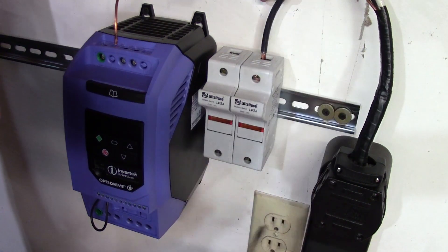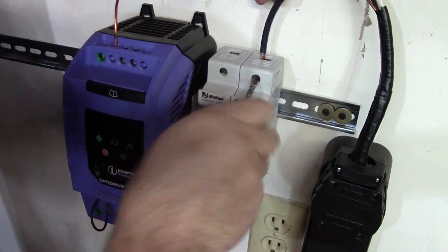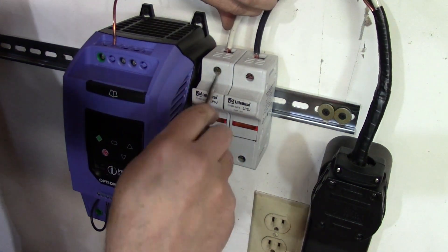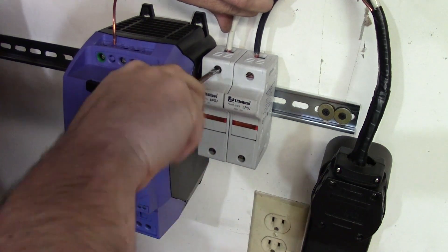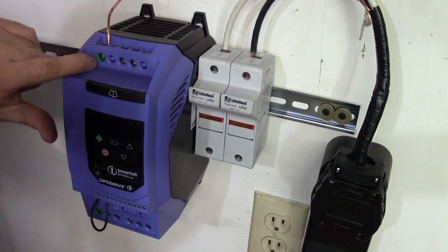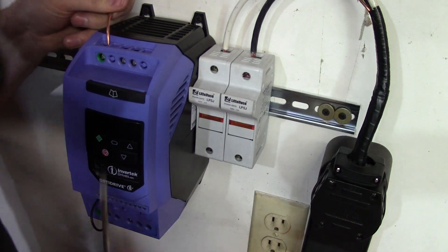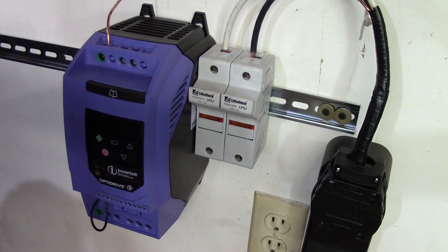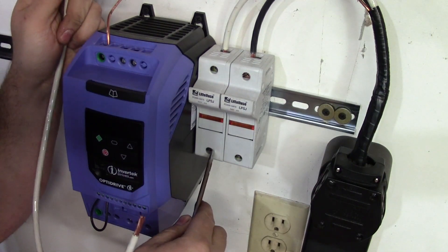You start by putting your first leg into the fuse and simply tightening down the lock screw. Insert the second leg into the second fuse and tighten down the lock screw. Now insert the ground wire into the green port marked ground. Take your little jumper wire here and you're going to go out the bottom of the fuse bank into the top of the Invertek.